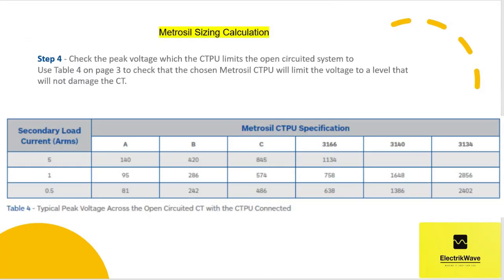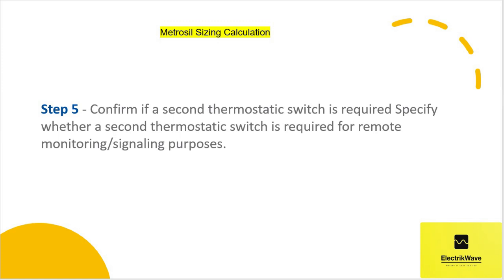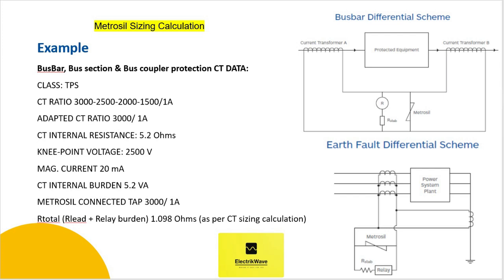Next. As per Step 4, check the peak voltage which the CTPU limits the open-circuited system to. Use Table 4 to check that the chosen Metrosil CTPU will limit the voltage to a level that will not damage the CT. Next. As per Step 5, confirm if a second thermostatic switch is required. Specify whether a second thermostatic switch is required for remote monitoring or signaling purposes. Next. Now let's see a practical example.